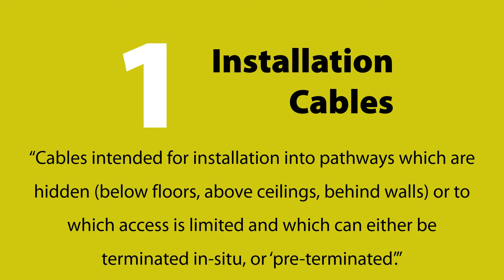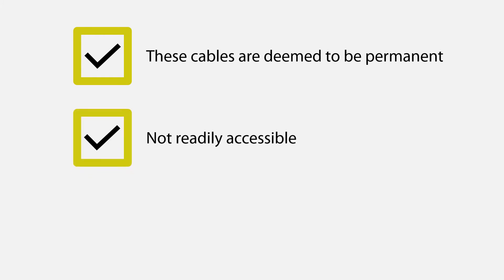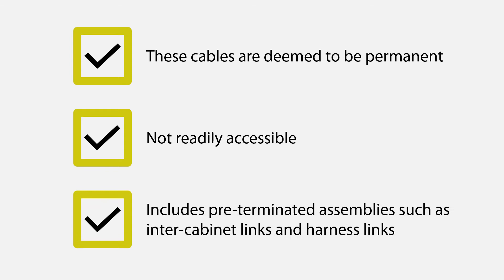The first covers installation cables and the actual clause is shown here. For further clarity, these cables are deemed to be permanent and not readily accessible. By the wording, this also includes inter- and intra-cabinet links such as harness links, even though some may mistakenly view these as long patch leads.